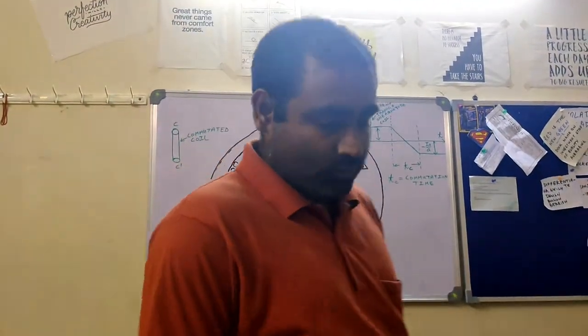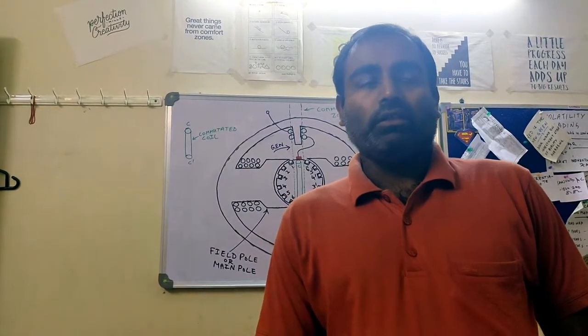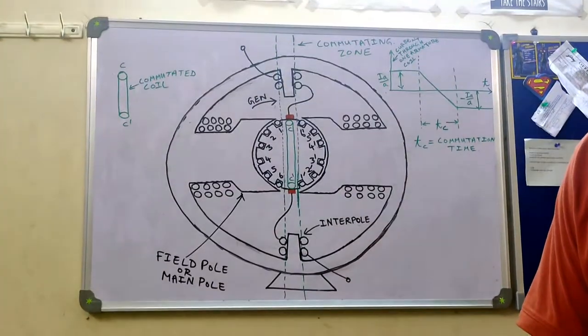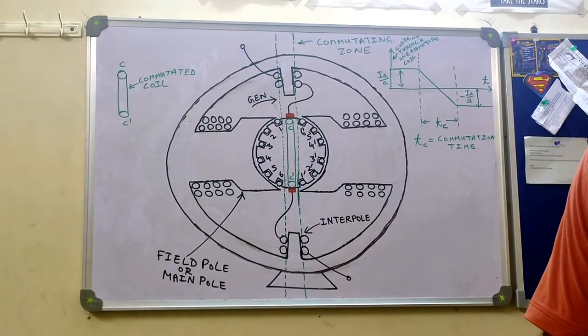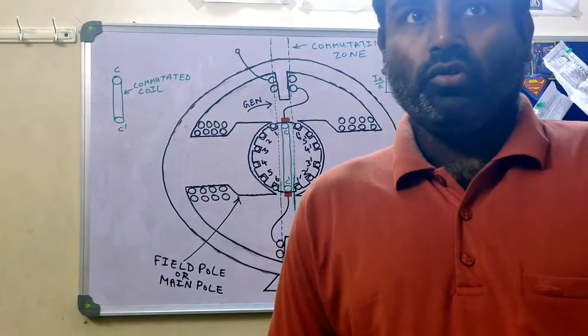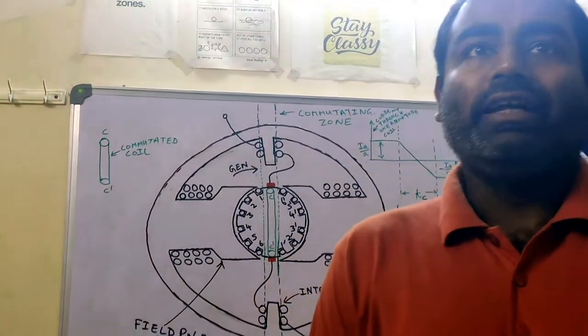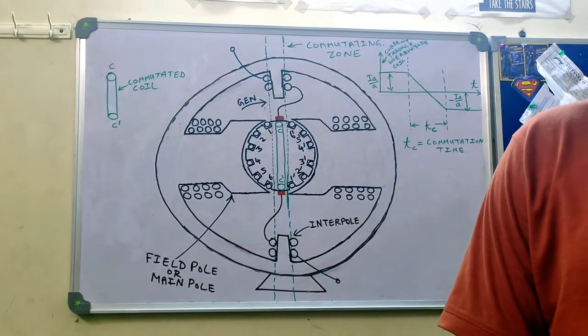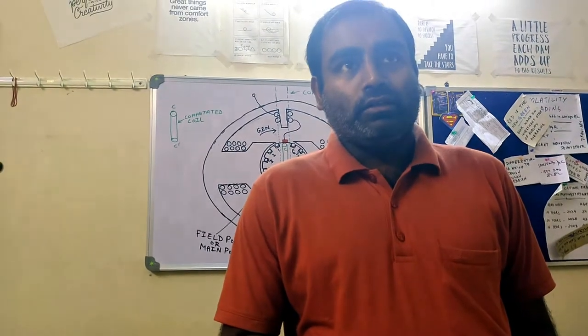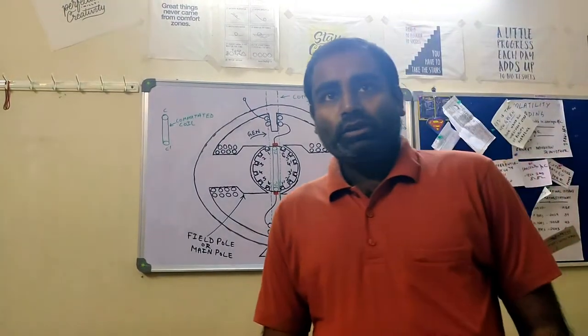Due to armature reaction, we see that there is a delay in commutation. By delay in commutation, we mean that the time taken for the reversal of armature coil current — the coil which is undergoing commutation — that time is increased, or rather the change of current through the commutated coil becomes slow. By the time the change is going to take place completely, the contact between the commutator segment and brush is broken, resulting in incomplete commutation. Because of that, there is sparking at the trailing edge of the brush.